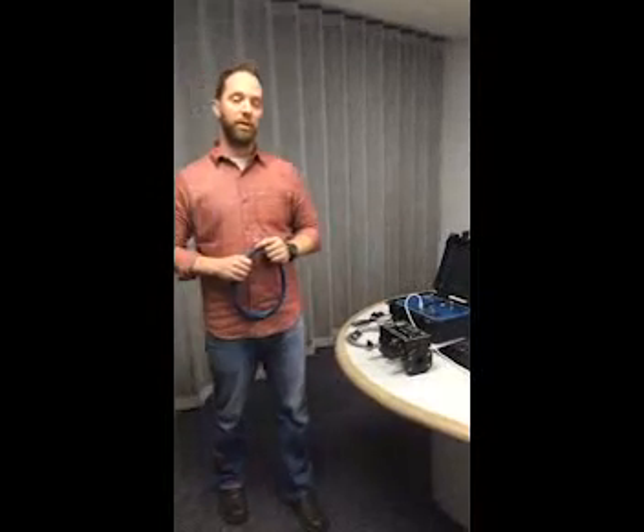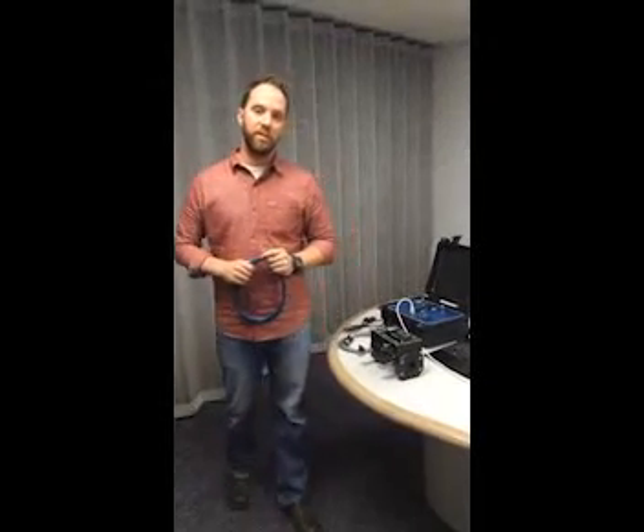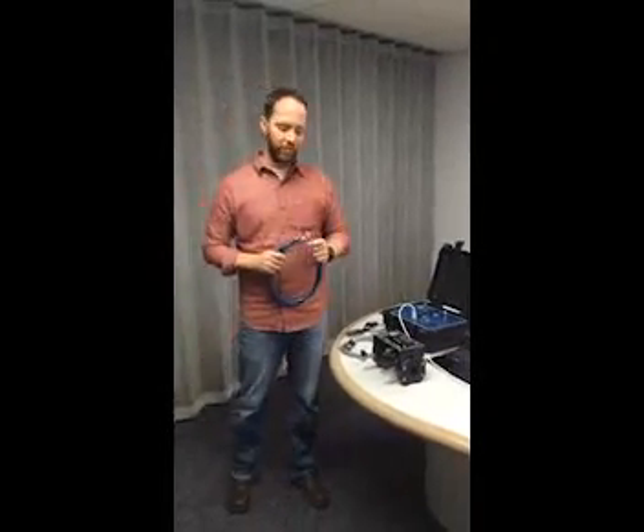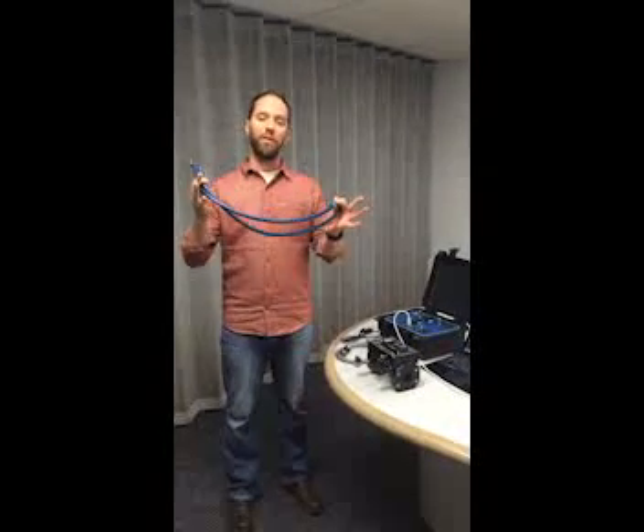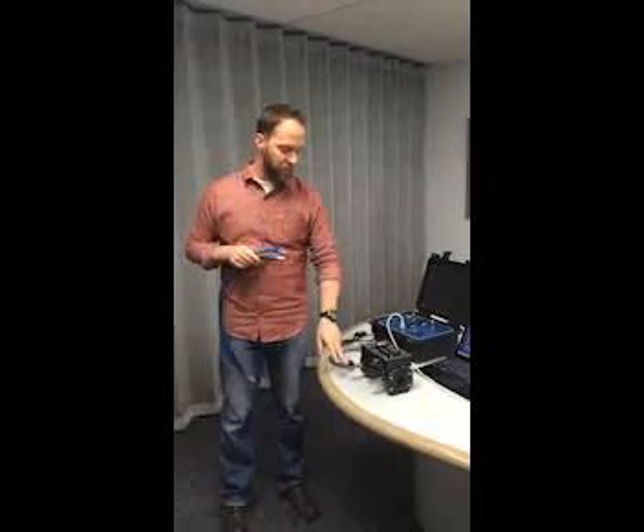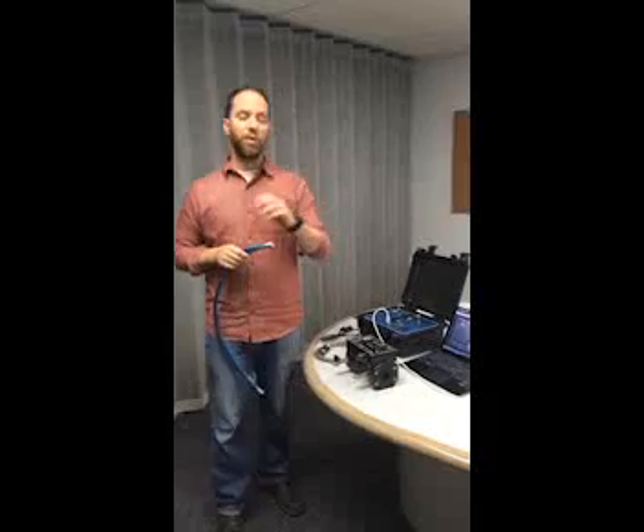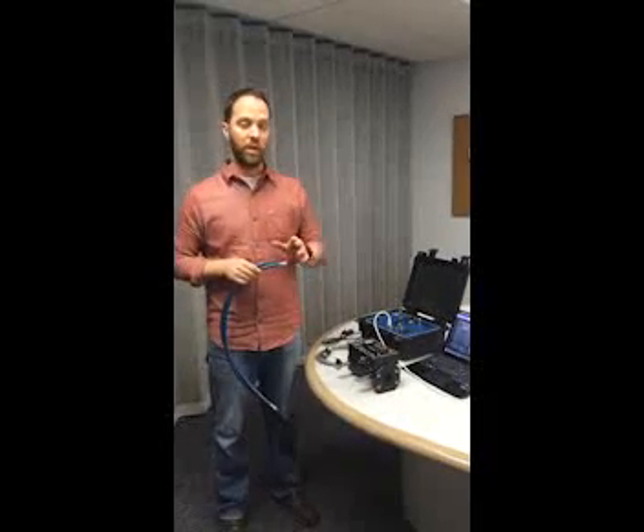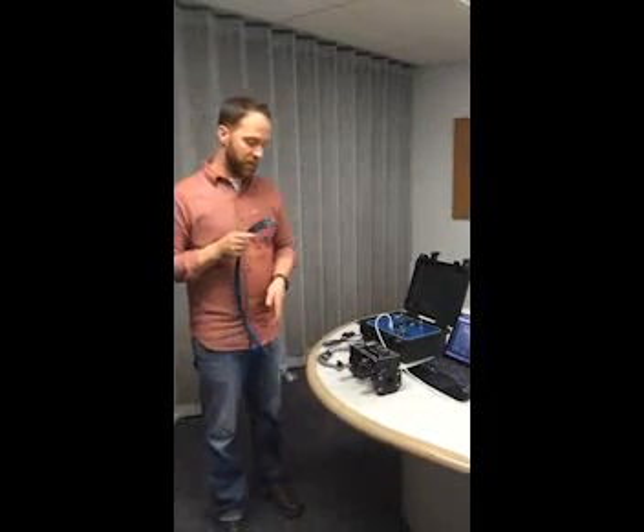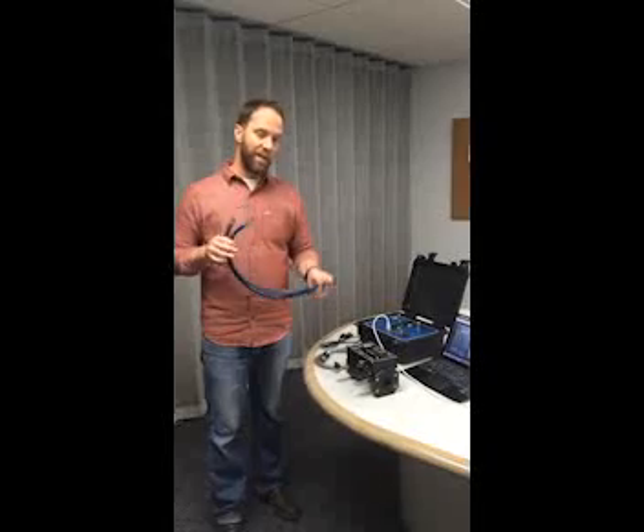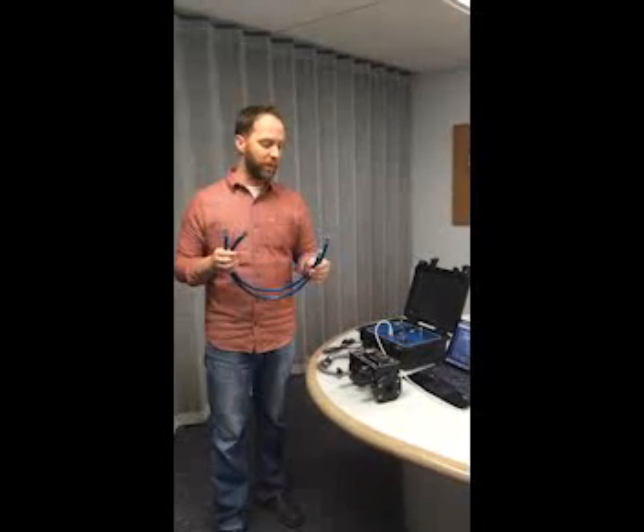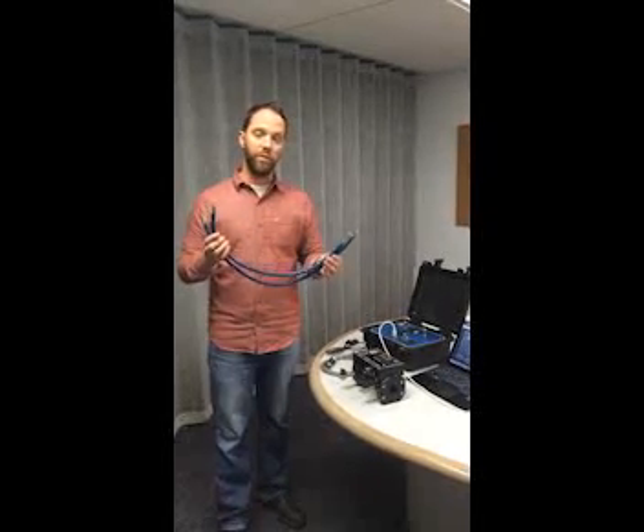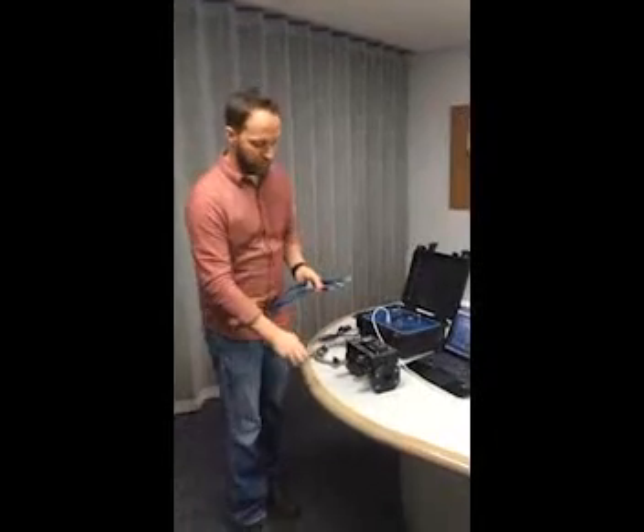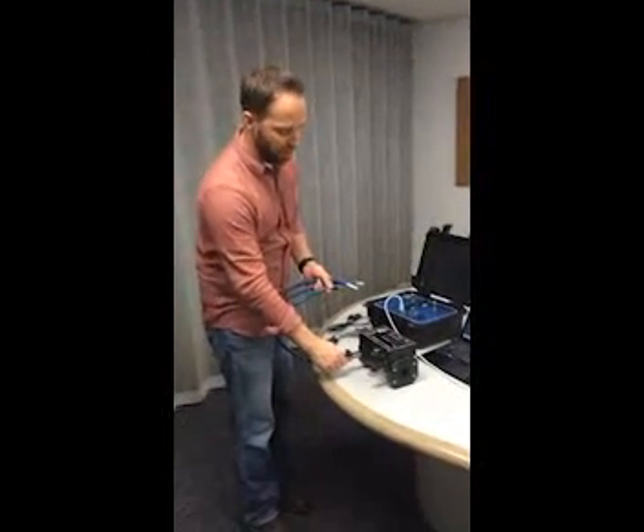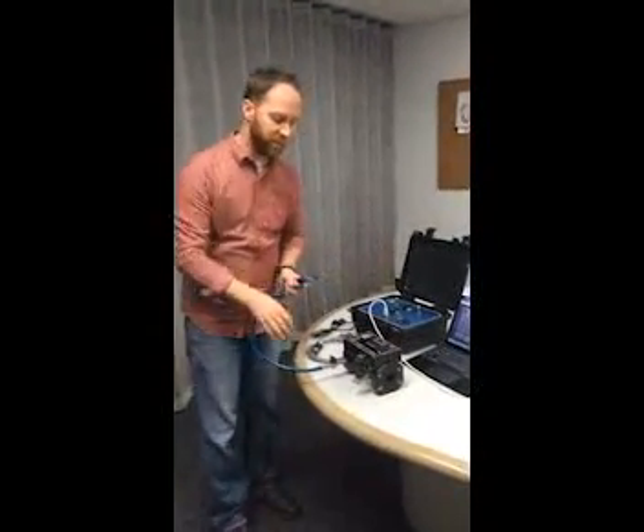Okay, for this next step, we're going to talk about what you need out in the field to successfully calibrate your FM50. You're going to need hoses, most importantly. You may already have these out there. They're going to connect the ball valve to the test set. Don't connect them yet. There's going to be a step where we actually do that, and it's important that you don't do that yet. But in case you go out to the field and you don't have them, you're going to need to make them. We recommend the shorter the better. 2 to 3 feet is ideal, and you'll be able to look at the connector between your ball valve and what's going to be required from the test set.